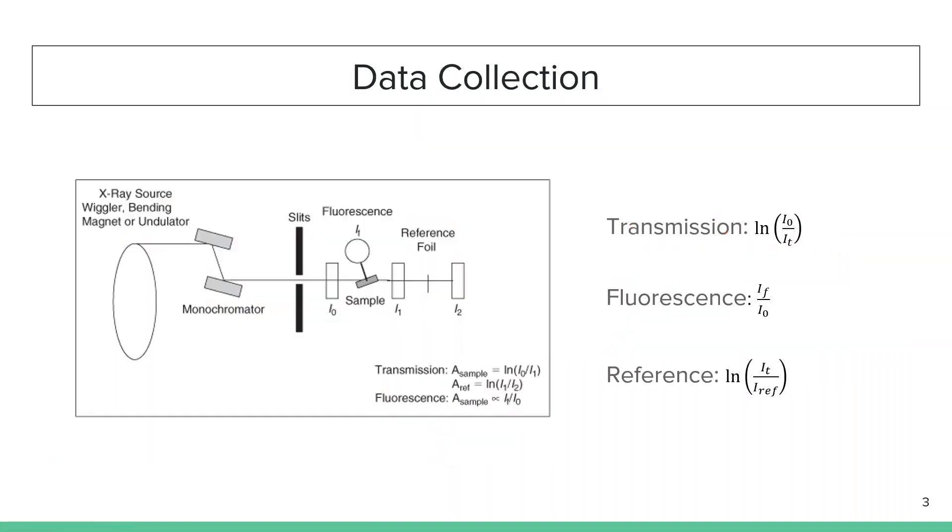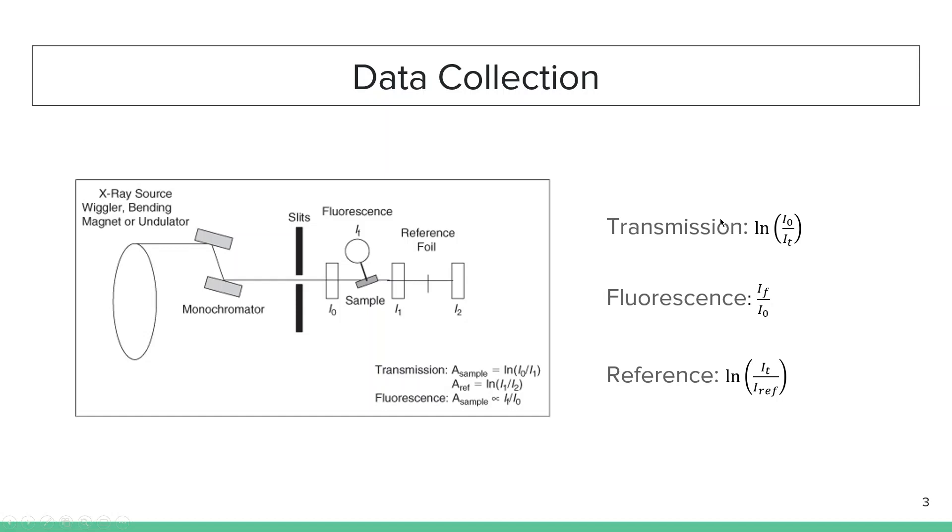Before jumping to data analysis and pre-processing, it's a good idea to know how data is collected at the beamline. This area is the region available in the hutch. All the other optics are generally taken care of by the beamline staff. Depending on your sample, you can prefer collecting data in transmission, fluorescence, or both. The beamline generally offers a reference channel, which comprises of a foil of the element you're working with.